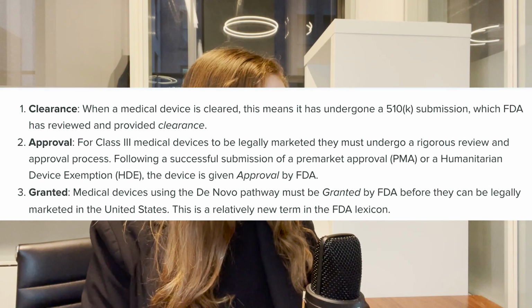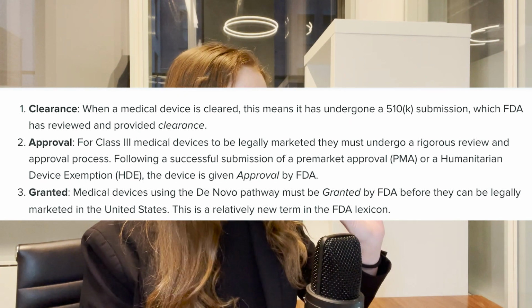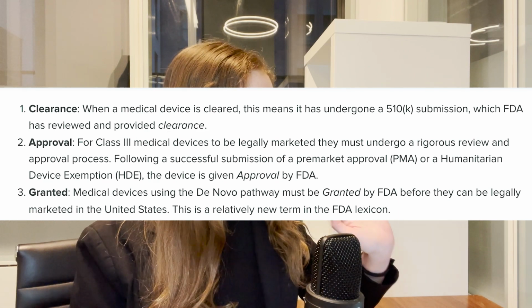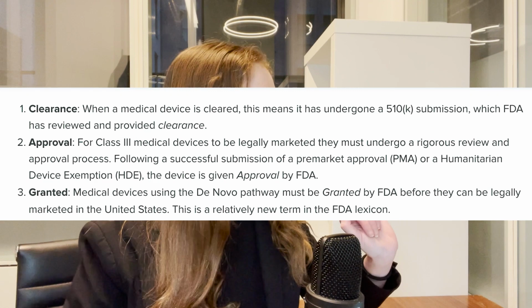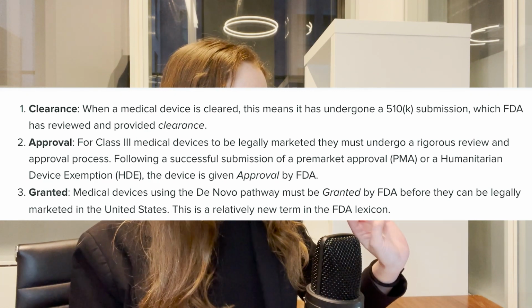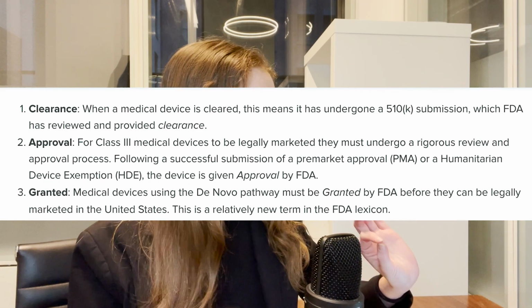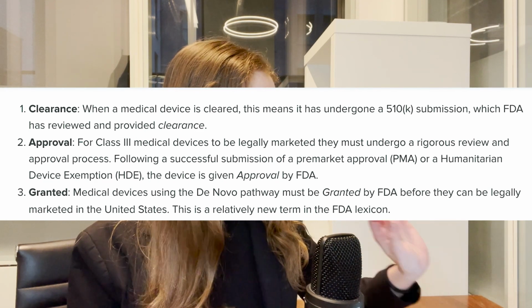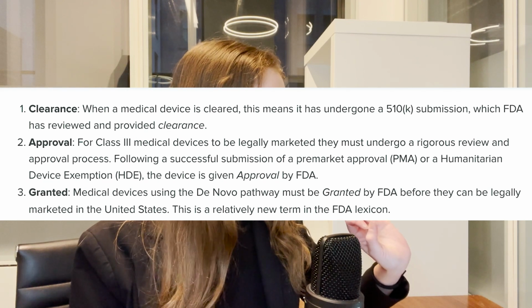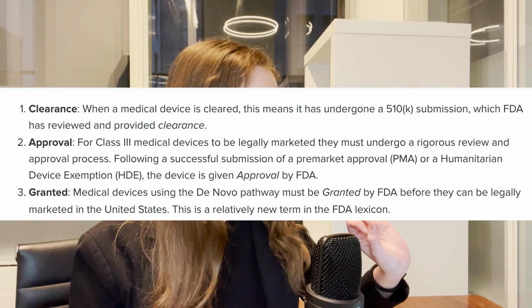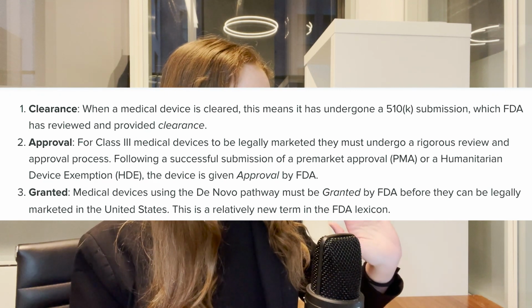Now, clearance is when a medical device is cleared. This means it has undergone a 510(k) submission, which FDA has reviewed and provided clearance. Approval: for Class 3 medical devices to be legally marketed, they must undergo a rigorous review and approval process. Following a successful submission of a pre-market approval, PMA, or humanitarian device exemption, HDE, the device is given approval by FDA. So after all of this is finished, either clearance or approval, it is available in the US market. So either one is really great. So this is great news that Nano-X, for example, got clearance, because it means that now they can market in the US.